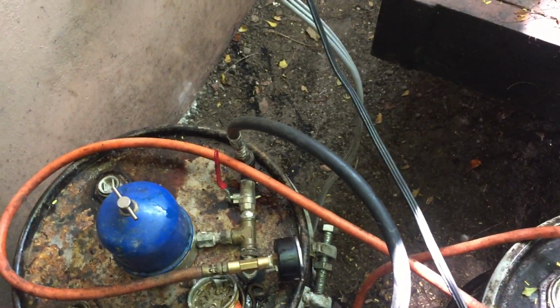You can see this oil is still cloudy. The centrifuge is going to have to run longer. It's not acceptable yet. If you compare it to these two, it looks more like the starting product than the final one. The other critical thing is that the oil has to be maintained at a certain viscosity.